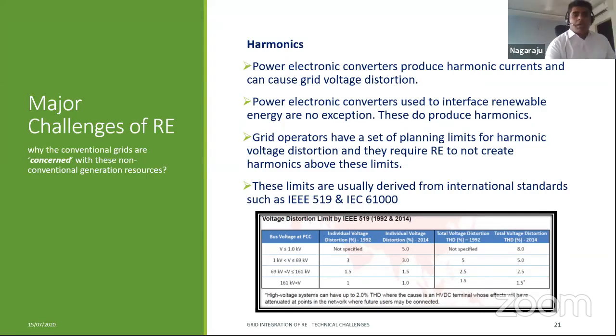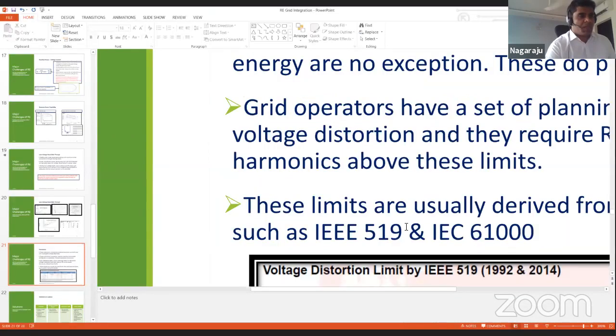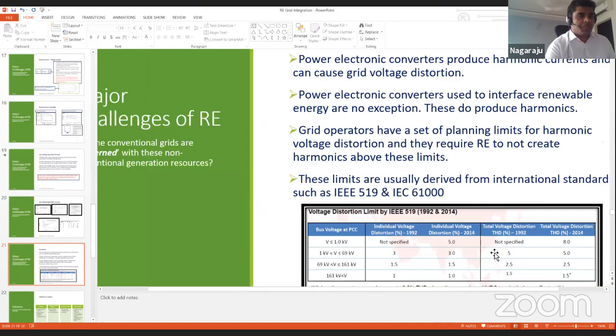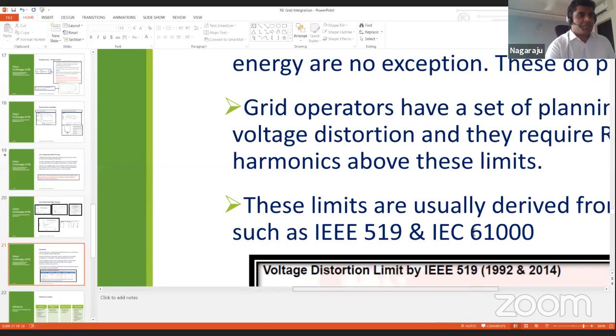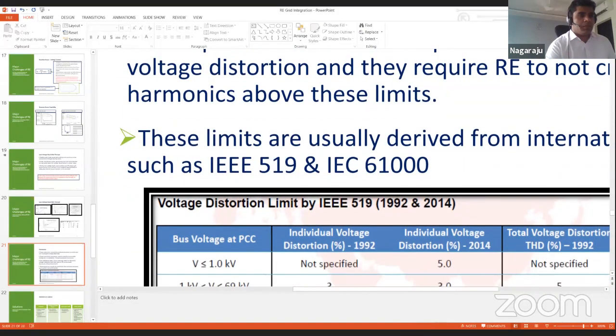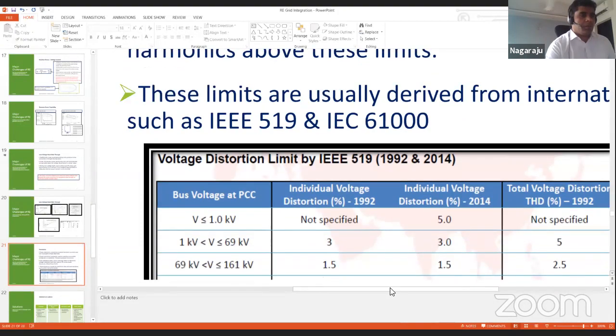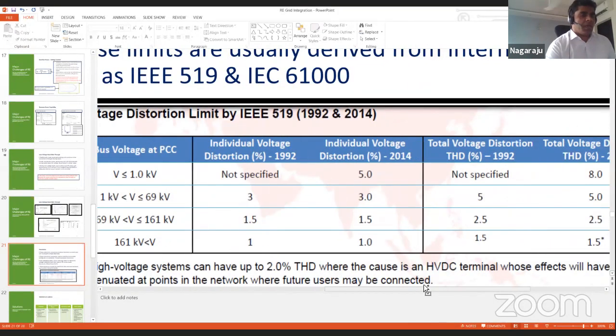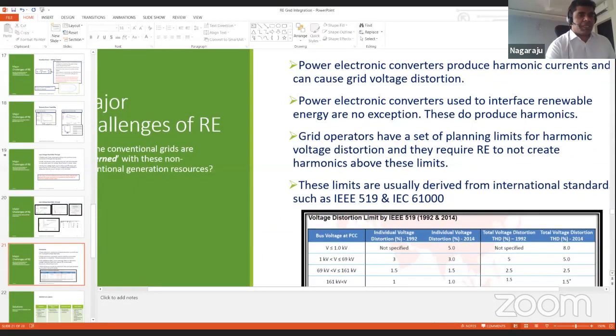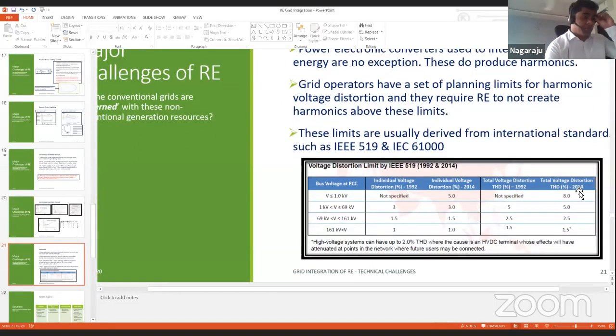So what is the requirement here? Let me zoom in a bit. I don't know how well you can see. So in terms of harmonic requirement, as per the new 2014 IEEE 519 standard, if the connection voltage is 161 kV or below, down to 69 kV, you can have 2.5% THD in the grid voltage.